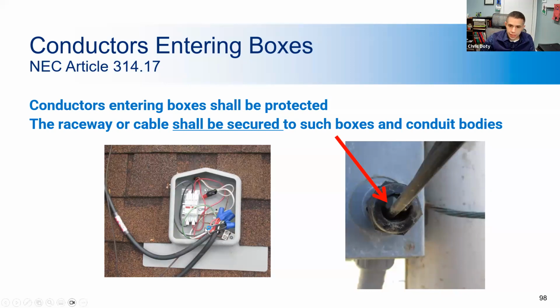And in the enclosure on the left, the flashing is good. It's up under the shingles, looks good. However, there are manufacturer knockout locations in this enclosure, and they were not utilized, right? They just ran the wiring up underneath the top, which would be installed on top of this, and you can't do that, right? Because that unseals it, makes it not weather rated, and eventually moisture will get in and water, and you have water damage, and obviously you don't want to have water in your electrical system. So that would definitely fail. They should disconnect these, run them all through the knockouts and have a proper fitting, and accomplish getting the connection in the enclosure that way.